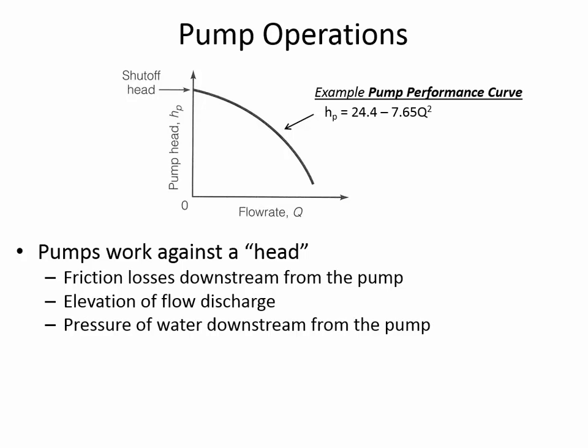All right, so when you get a pump from a manufacturer, they'll have a table that describes how it operates, or it may be depicted graphically like this. The way this diagram works is that it can lift the water only a certain amount of elevation. Here is an equation. It's not always 24.4 minus 7.65; this is just an illustration of the form of the equation. This 24.4 is the intercept on the y-axis. And so at most, this particular pump can lift water 24.4 meters.